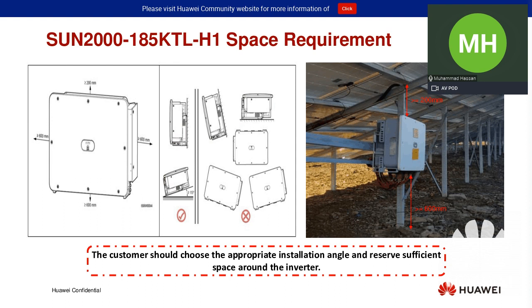Space required. This is very important for the 185 KTL. This is a high power inverter, so you need to follow the instructions provided by us, that these inverters should have approximately minimum 600 mm distance from the other inverters, so that the heat will be dissipated from the inverter. It's a high power inverter, which generates more heat. So you need to use the recommended heights or space available on 4 sides of this inverter, so that the heat totally dissipates. If there is any other inverter installed, or if there is less space available from the other inverter, then perhaps the heat will not be totally dissipated, and you will start facing some problems as well.